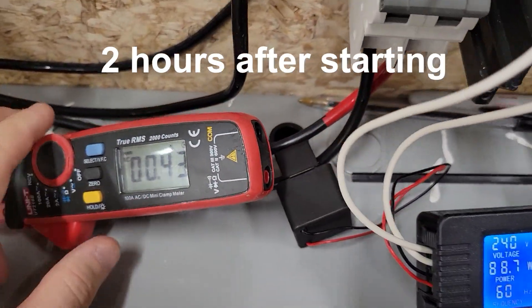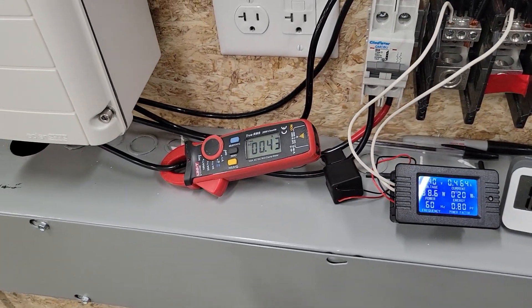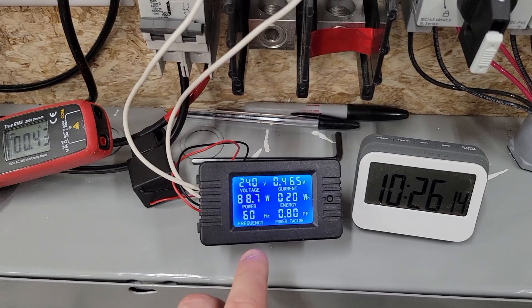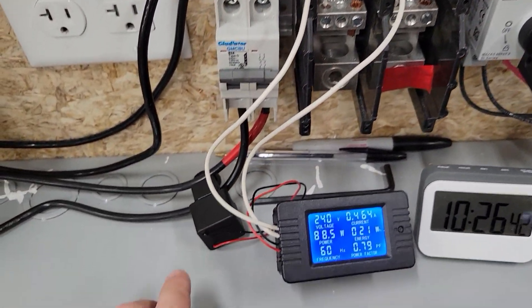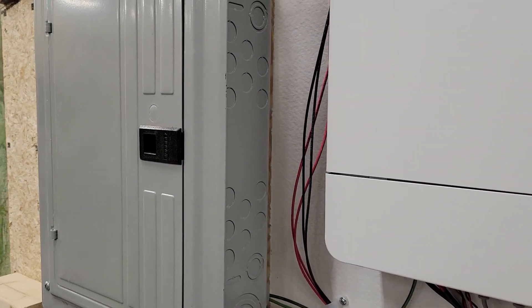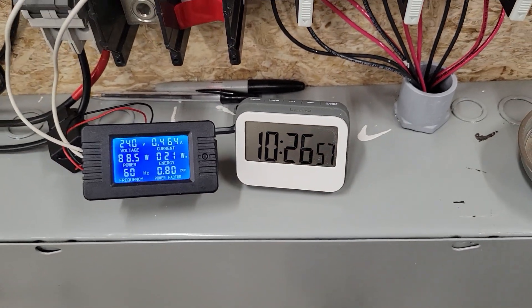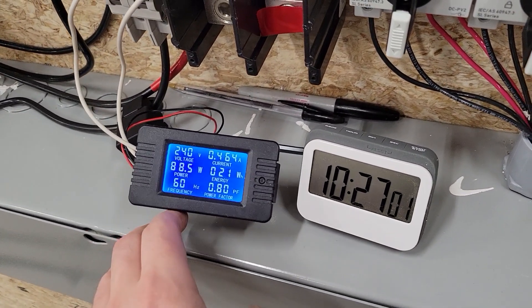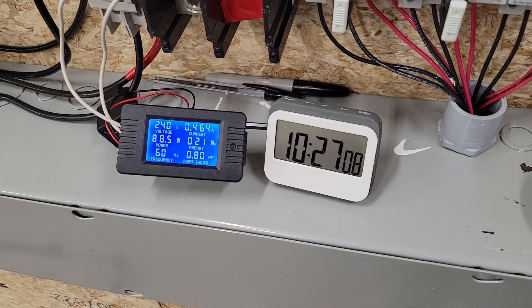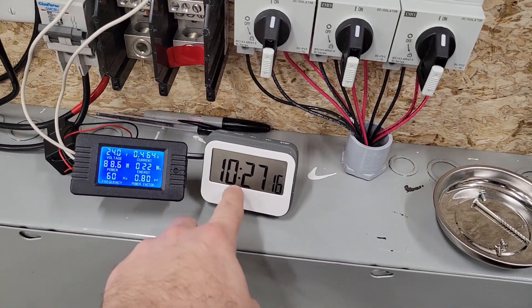A little update: I have noticed the amps have finally dropped. We were around 3 amps for a bit and now it's finally dropped down, which tells me we have finally reached the set point of 66 degrees Fahrenheit in the garage. So I added this meter and just zeroed it out. It's running off 240 volts and we have a CT clamp right here on the leg feeding into the panel — the only thing running on the panel is the mini split right now. I just zeroed out the watt hours. We're going to come back tomorrow at 10:30 in the morning to get 24 hours of runtime and see how many watt hours it uses. Right now it's going to hit the low 30s today and then drop back down overnight, but I'll let everybody know what the nighttime low is tonight in this 24-hour range. Right now it's 10:30 a.m.